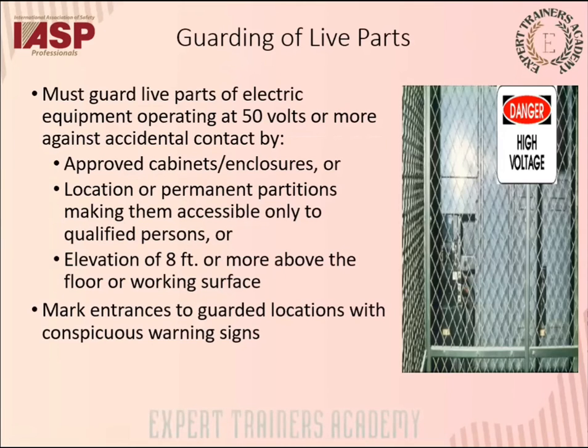Guarding the live parts. So basically barricading. It can be either approved cabinets or enclosures. It can be permanent partitions. So there must be an elevation of 8 feet or more above the floor or working surface. Mark entrances to guarded locations with conspicuous warning signs. Like in the picture, we could see it mentions danger, high voltage. So you can warn using signages.